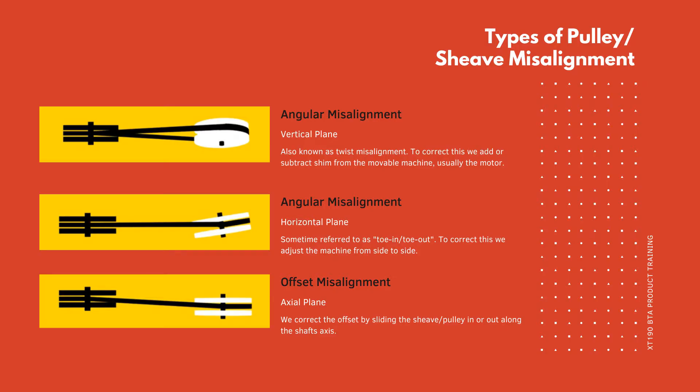There are three types of pulley or sheave misalignment. The first is angular misalignment in the vertical plane, also known as twist misalignment — to correct this we add or subtract shim from the movable machine, usually the motor. The second is angular misalignment in the horizontal plane, sometimes referred to as toe-in or toe-out — to correct this we adjust the machine from side to side. The third and final type is offset misalignment in the axial plane — we correct the offset by sliding the sheave or pulley in or out along the shaft's axis.